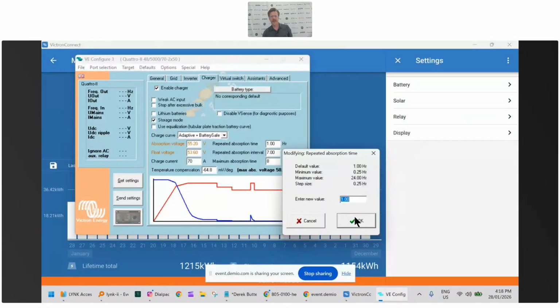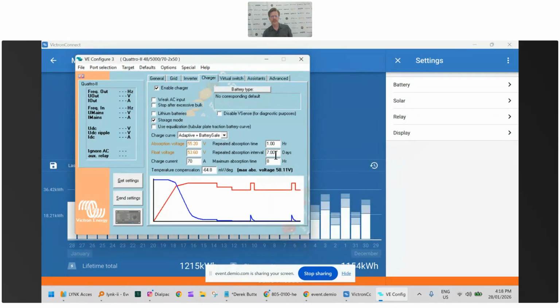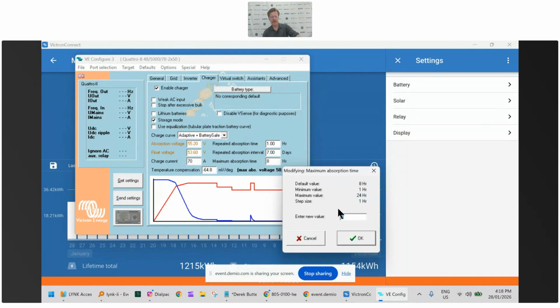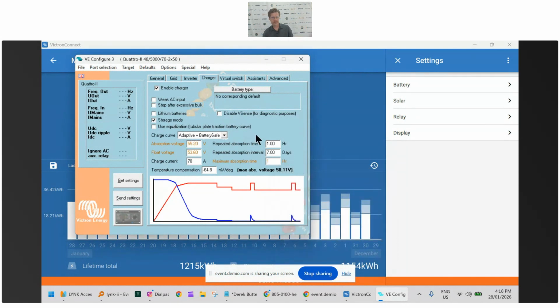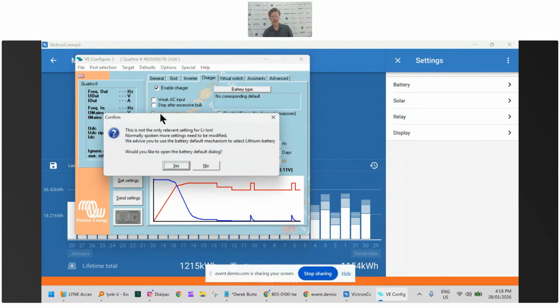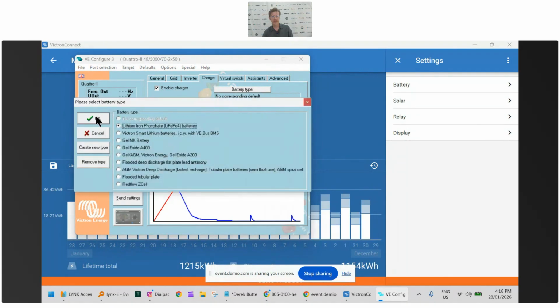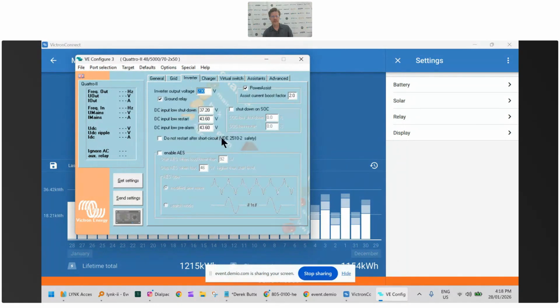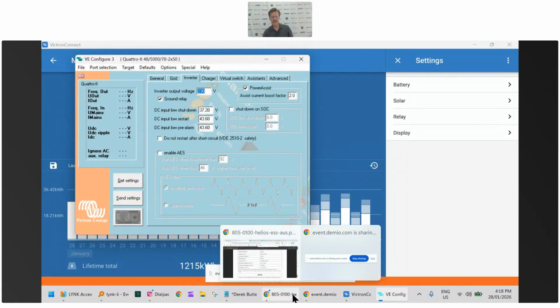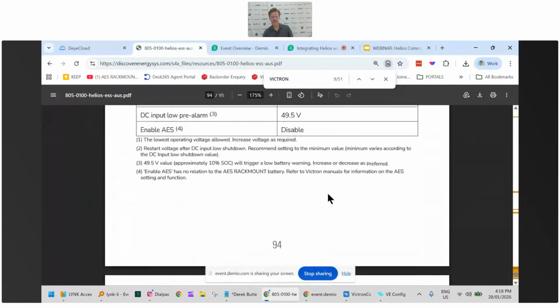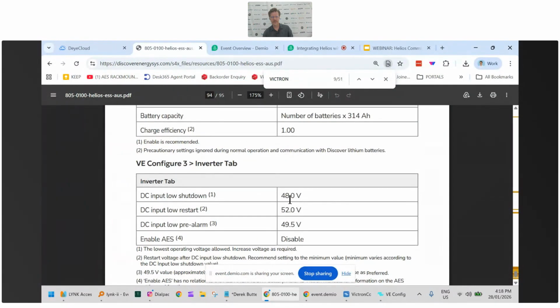because it has to be more conservative when it's not talking to the inverter. The specs are in the manual, but it's 1 hour repeated absorption time, 7 days interval, and 1 hour for this as well. And you want it on lithium batteries as well. You also need to set the low voltage disconnection values. And those are here: 48, shut down, restart at 52, and the alarm 49.5. So these are just set here.